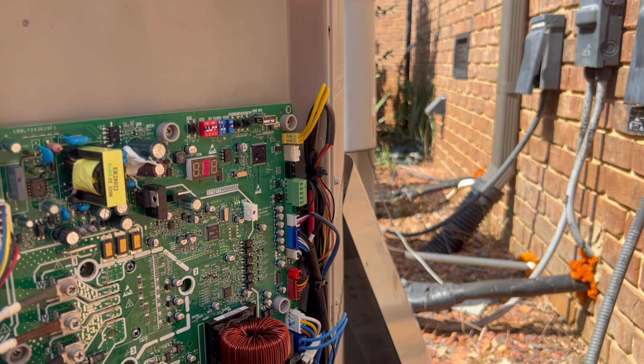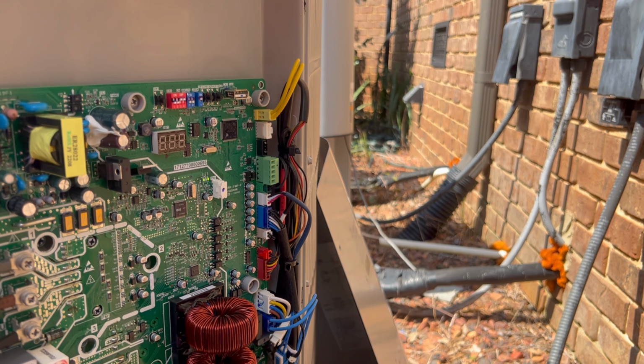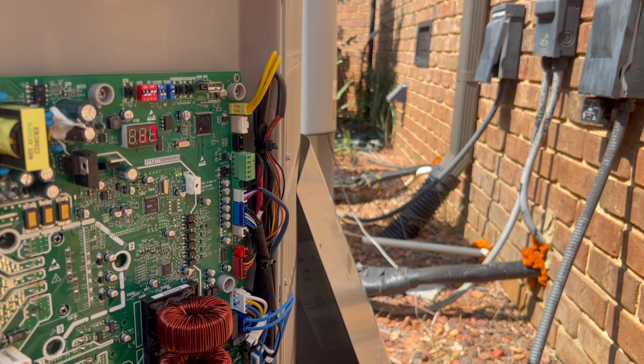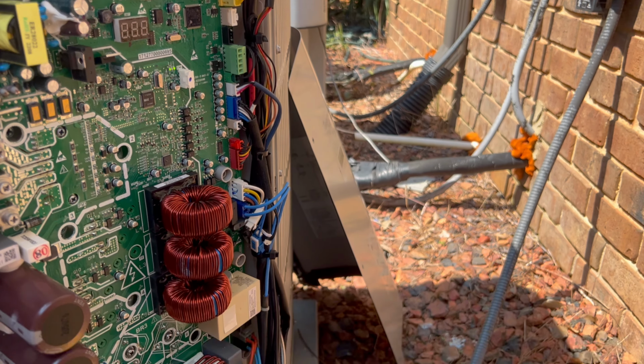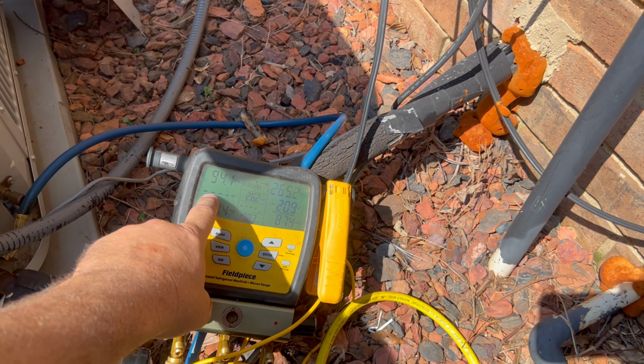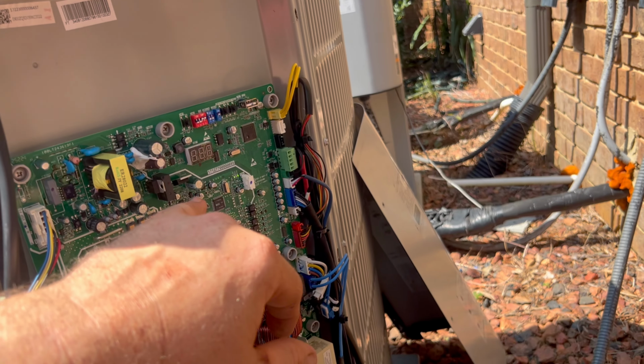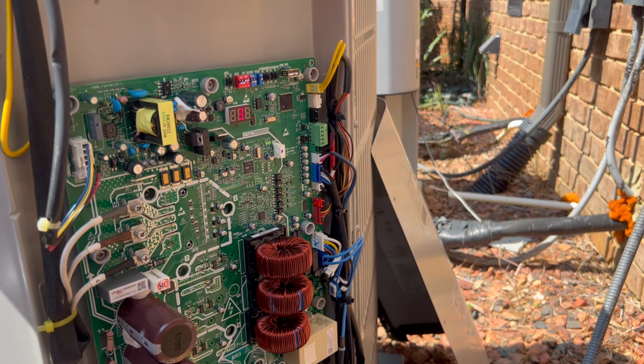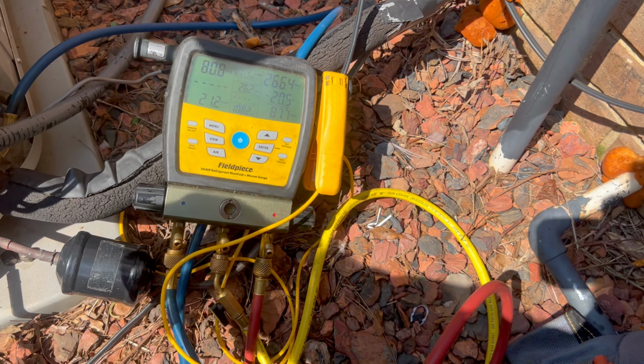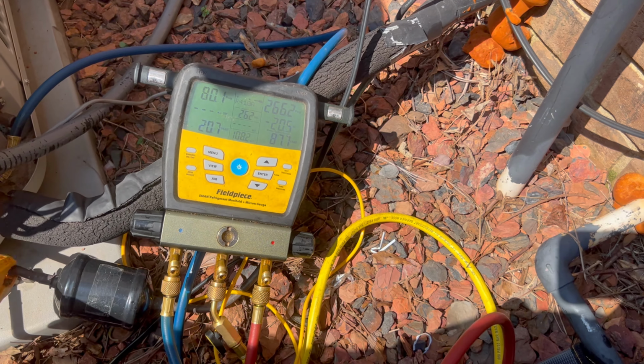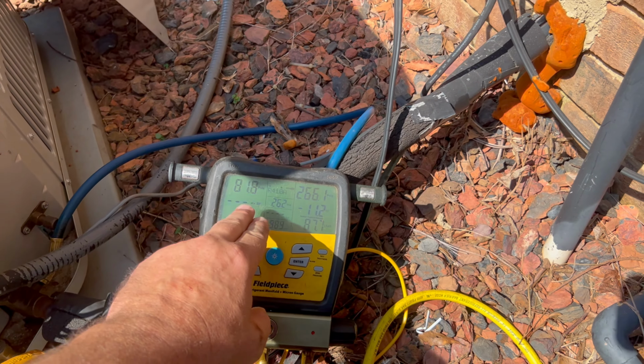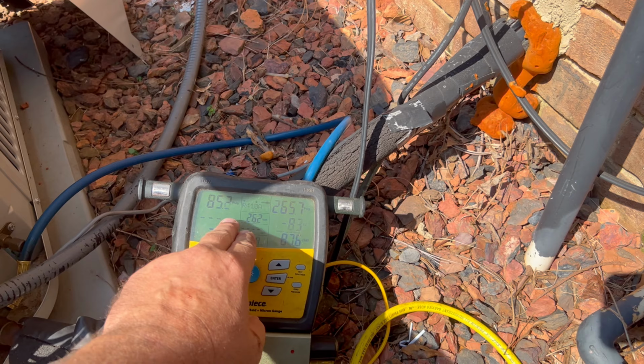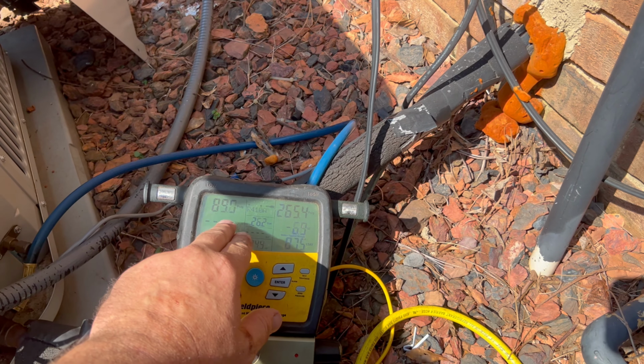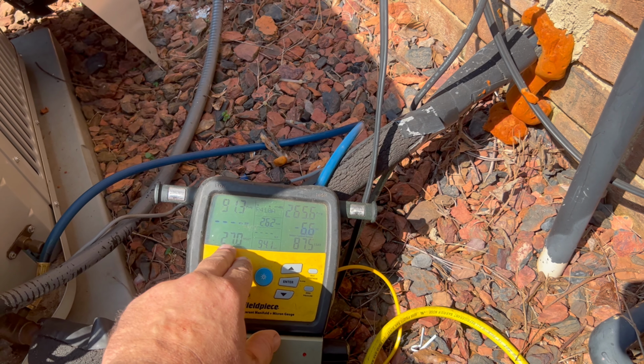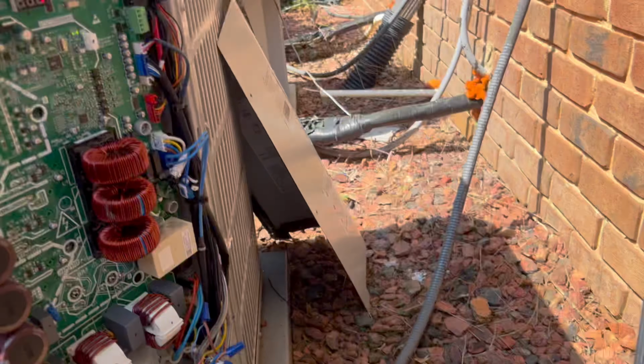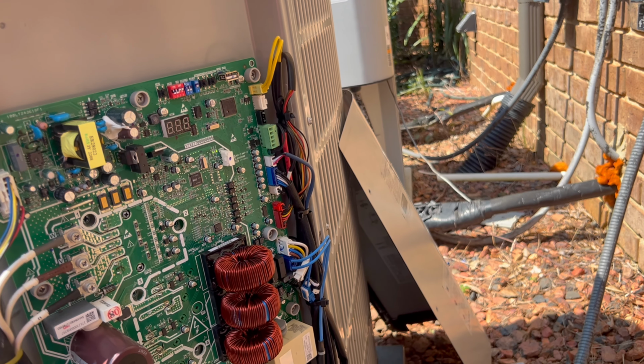And again, this guy is actually monitoring using that pressure transducer, ambient temperature controls, and coil temperature controls. It's going to modulate itself around a little bit, but something you do have to remember with them is if you are low on refrigerant, which we are because we haven't completely charged the system, it will not allow it to ramp up all the way, so you never really see what you're running. So it's very possible to come across these, look at your gauges, check your subcooling, and everything looks more or less right, and in reality it is not. You can see it doing it right now, backing off the inverter compressor to a point that it's not going to be below freezing any longer. So you may see one that looks perfectly fine, and you might look over here and say, oh, we're only running 30%. Wonder what it does when we run a higher percentage.